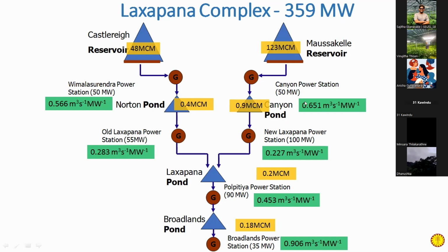Then you can see this yellow colored label - this is a much important value. In a hydropower station, the discharge rate is a much important parameter. This is the discharge rate of the Vimalasurendra power station, and you can see its unit: cubic meters per second per megawatt. That means if you are operating this Vimalasurendra power station at 1 megawatt, then per second, during that 1 second, 0.566 cubic meters of water will be discharged.